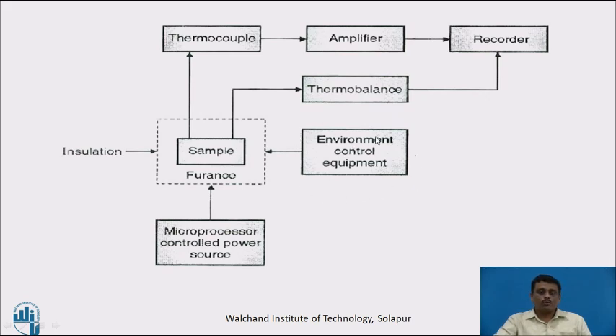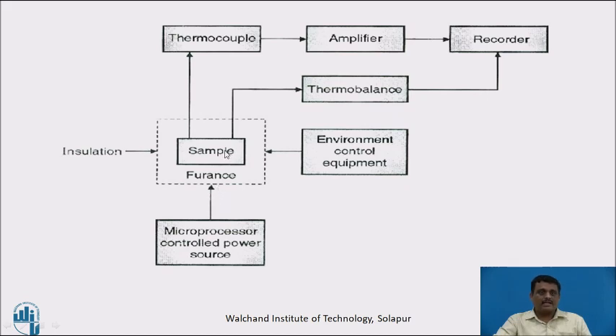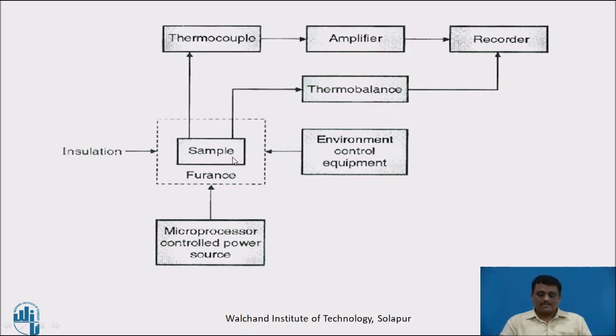There is also environment control equipment. Its role is to maintain an inert atmosphere around the sample while it is being heated, because there is a possibility of the sample reacting with atmospheric impurities and being converted to unwanted by-products. To avoid this chemical reactivity, the environment control equipment provides a flow of inert gases across the sample.